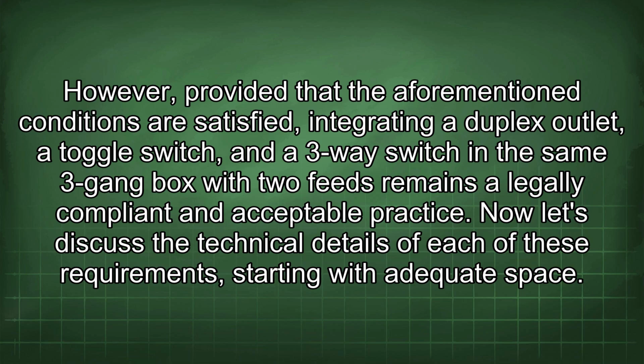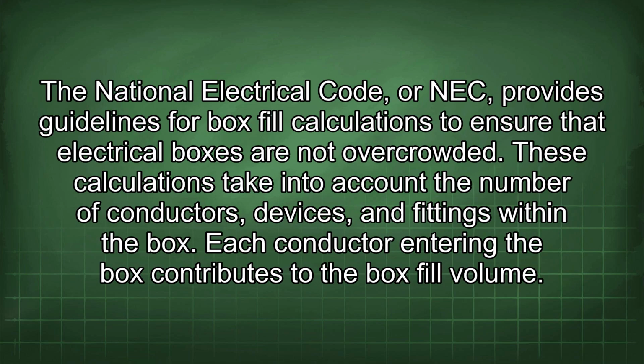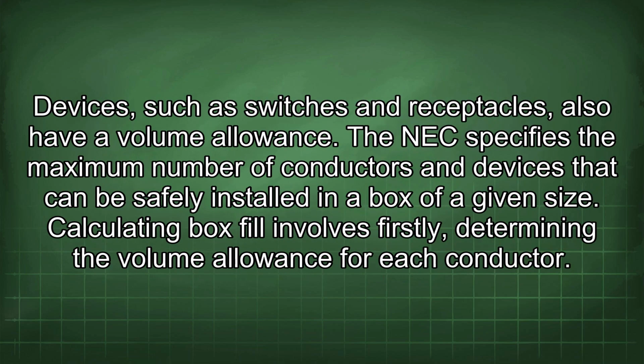Now let's discuss the technical details of each of these requirements, starting with adequate space. The National Electrical Code, or NEC, provides guidelines for box fill calculations to ensure that electrical boxes are not overcrowded. These calculations take into account the number of conductors, devices, and fittings within the box. Each conductor entering the box contributes to the box fill volume. Devices, such as switches and receptacles, also have a volume allowance. The NEC specifies the maximum number of conductors and devices that can be safely installed in a box of a given size. Calculating box fill involves firstly determining the volume allowance for each conductor.